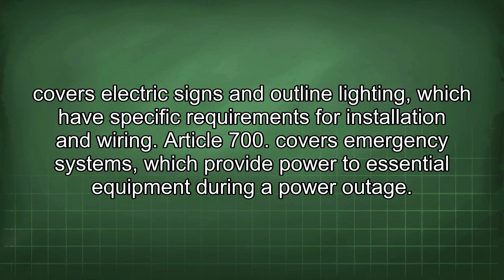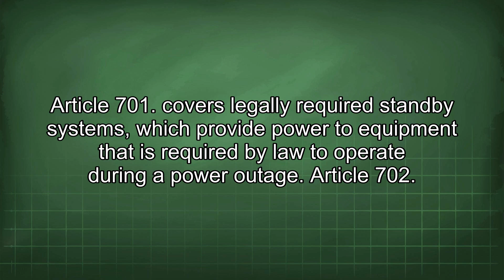Article 700 covers emergency systems, which provide power to essential equipment during a power outage. Article 701 covers legally required standby systems, which provide power to equipment that is required by law to operate during a power outage.